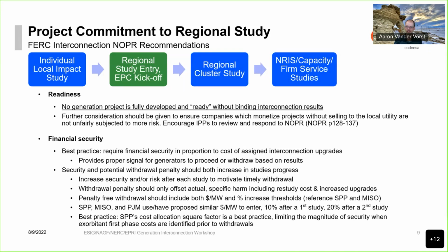However, the selection of a generator that does not have interconnection results in the solicitation process may lead to load reimbursing the generator for high transmission costs through transmission credits. Either way, selection of a generator before interconnection results are known poses significant financial risk that may result in suboptimal generators being built. Signing a PPA or bidding into an RFP without knowledge of interconnection costs and without schedules will result in broken contracts, generation capacity shortages, unmet customer needs, and/or high transmission costs to load.